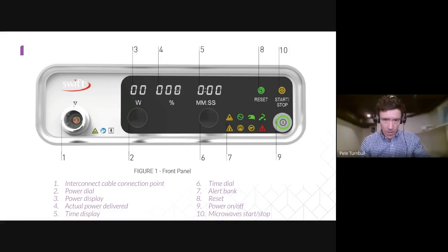And then what this display here is trying to say is how many joules of energy we are trying to deliver to the tissue. So if it's 8 watts for 2 seconds, that's 16 joules of energy. So the machine is measuring what percentage actually got delivered to the tissue so that you're not missing it. And if there's bad contact, it'll actually alarm the system. So if the patient shifts during the dose or moves away or pulls their foot away, what you'll get is that it'll stop delivering energy. So it's a safety mechanism.